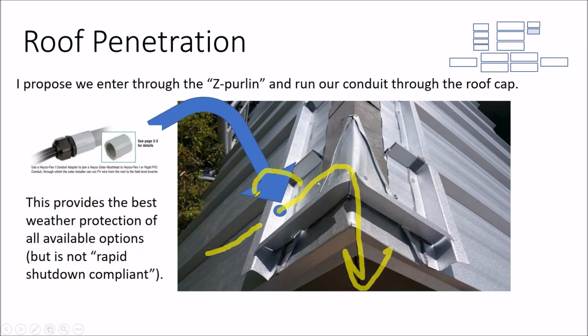There's code requirements that if you're boring straight through metal, you have to make sure induction isn't going to heat up a ferrous metal. There's also temperature derating if you're below half an inch from the roof deck, and it's pretty extreme derating, plus derating for the number of wires in a conduit. We had to take all of that into consideration.